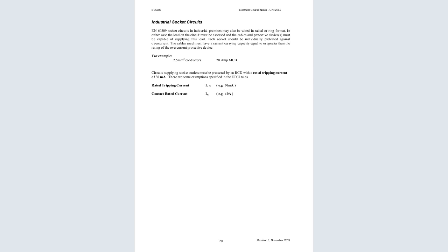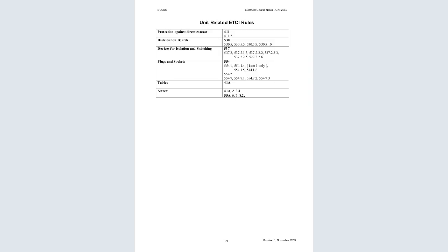Industrial socket circuits. The socket circuits in industrial premises may also be wired in a radial or ring format. In either case, the load on the circuit must be assessed, and the cables and protective devices must be capable of supplying this load. The socket should be individually protected against overcurrent. The cable used must have a current carrying capacity equal to or greater than the rating of the overcurrent protection. So sometimes calculations are done to get the rating of the sockets. Now the distribution board, and these are just the codes for the industry. Up to that point, can I have any questions?